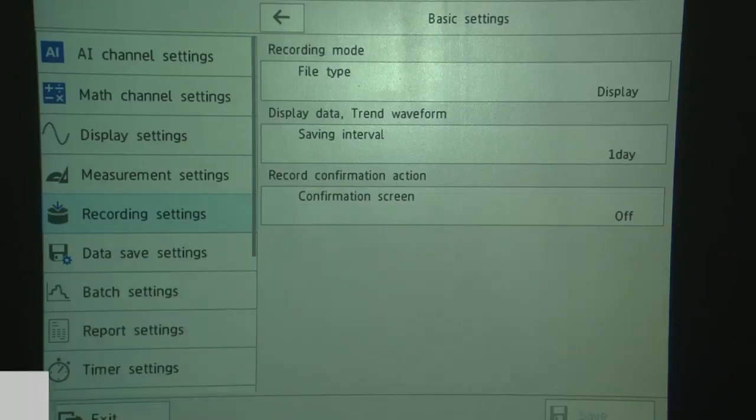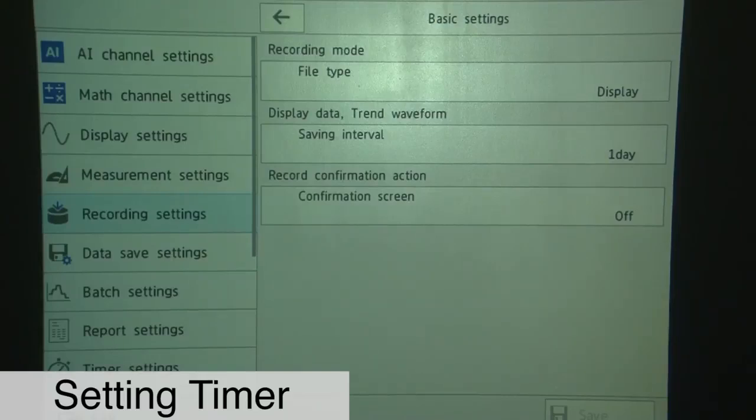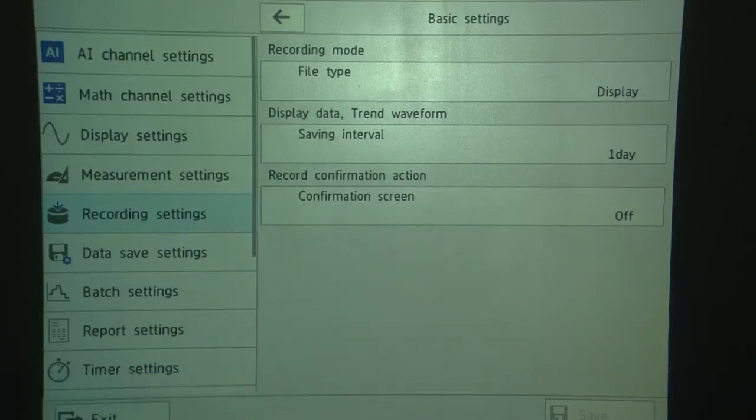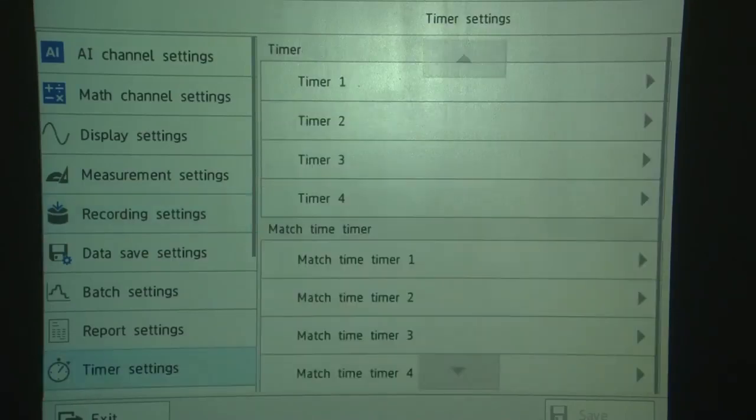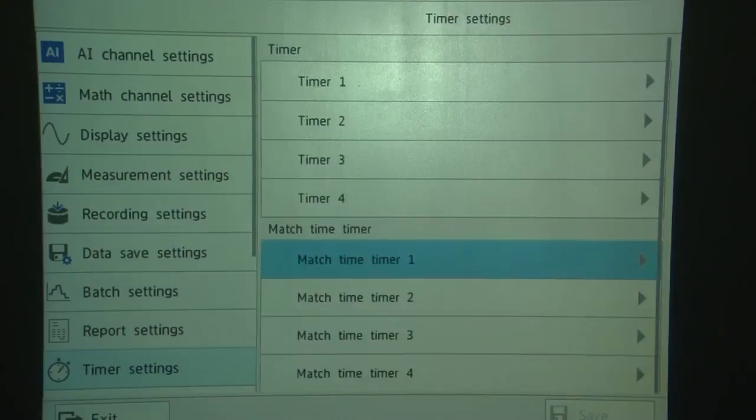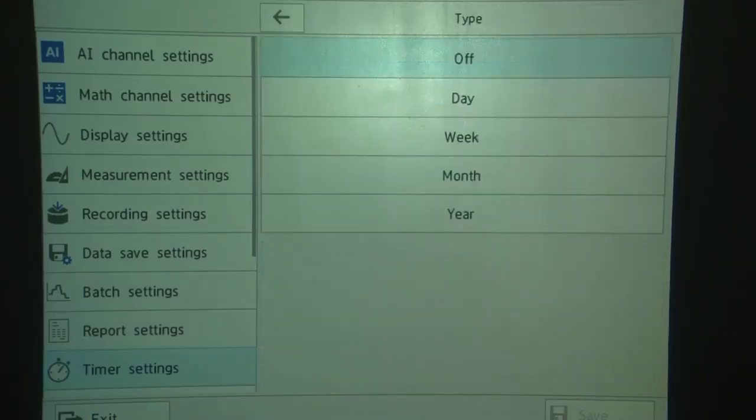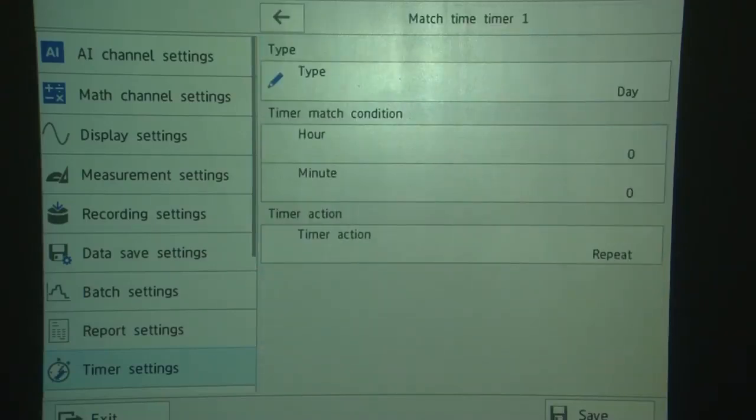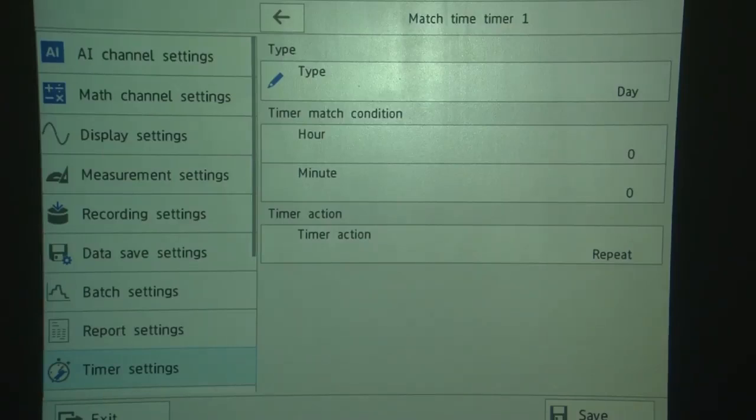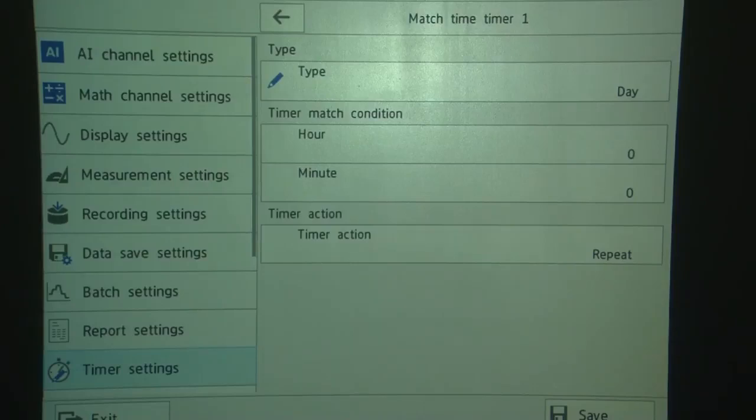The next thing we're going to do is set a timer. The timer is going to tell the machine when to start recording a new display file. So we're going to touch the timer settings. We're going to use what's called a match time timer. We're going to set it to day. And then by default, the hour and minute is 00, which is 12 midnight. And the timer action will be repeat. And we're going to touch Save.